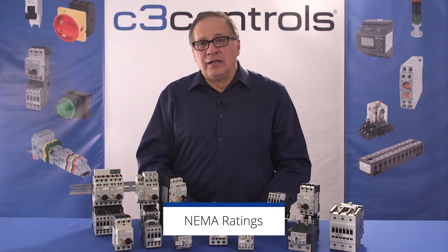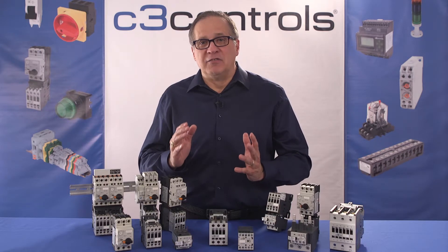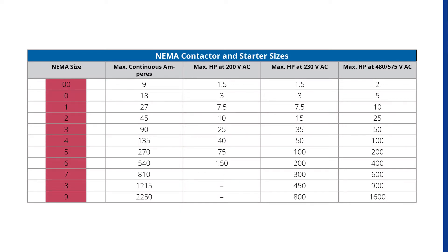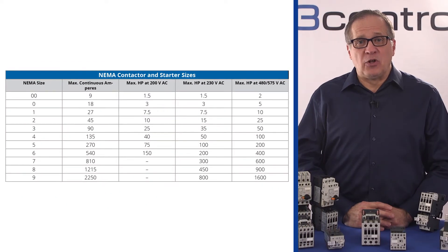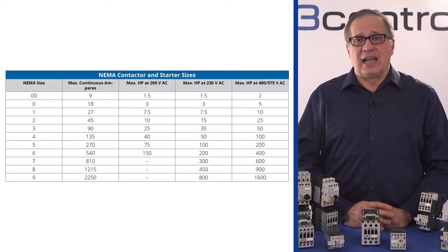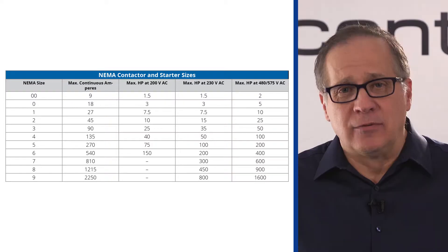The NEMA rating of a starter depends largely on the maximum horsepower ratings given in the National Electrical Manufacturers Association ICS2 standard. The selection of NEMA starters is done on the basis of the NEMA size, which varies from size 00 to size 9. The NEMA starter at its stated rating can be used for a wide range of applications, from simple on-off applications to plugging and jogging applications, which are actually more demanding.